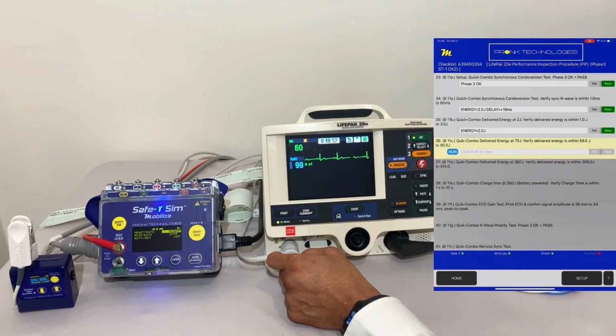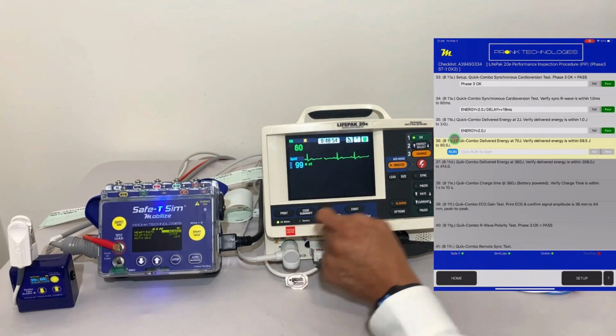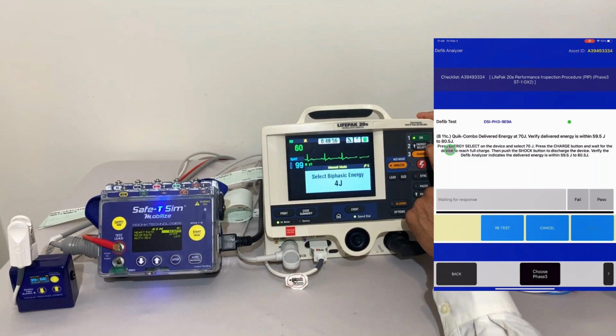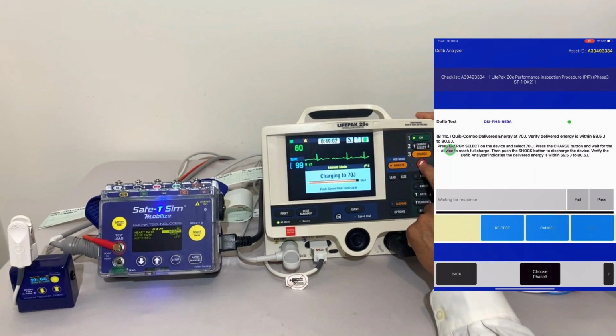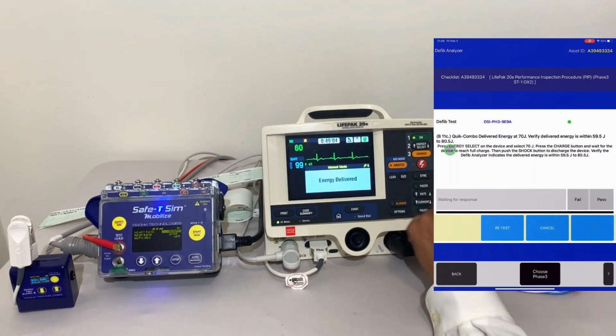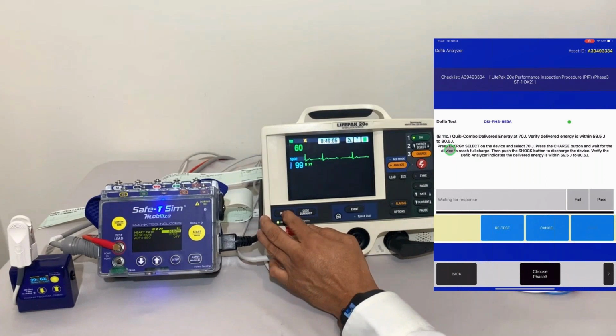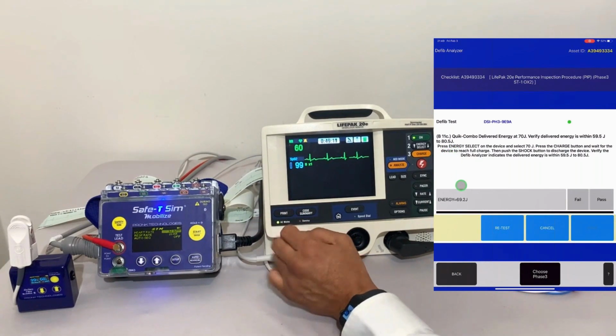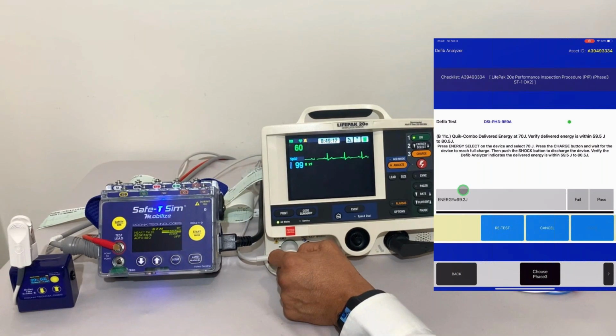The next test is 70 joules. Let's run that test. I'm going to charge the defib to 70 joules this time. And we're going to go ahead and charge it. Fire it. Again, the defib analyzer is going to confirm that we got the energy at the right result. And this result was 69.2 on a target of 70, and our range is 59.5 to 80.5. You know that's a pass as well.